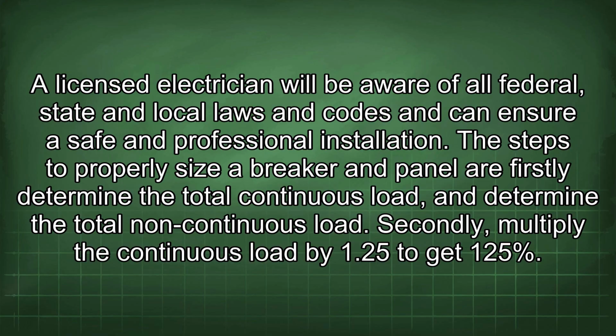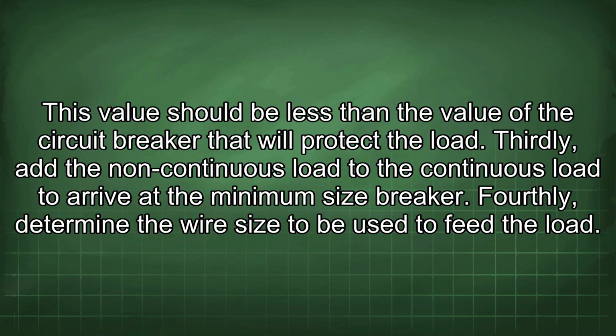The steps to properly size a breaker and panel are: firstly, determine the total continuous load and determine the total non-continuous load. Secondly, multiply the continuous load by 1.25 to get 125%. This value should be less than the value of the circuit breaker that will protect the load. Thirdly, add the non-continuous load to the continuous load to arrive at the minimum size breaker.